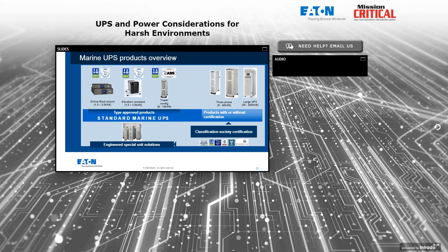So we would want to choose a UPS that offers those certifications and has been tested in the harsh environments that we see on shipboard that we might not see in an inland factory, for example. So three-phase, single-phase UPSs, rack mount, standalone, vibration isolator mounts. If you look closely, you can see the vibration isolator mounting at the bottom and in some cases at the rear of these UPS cabinets.